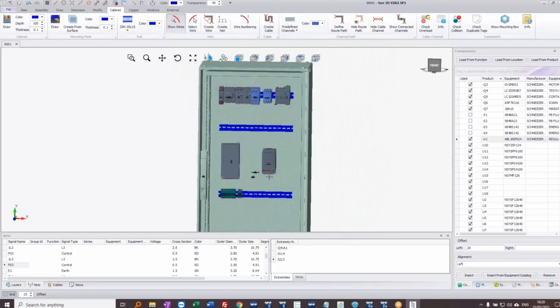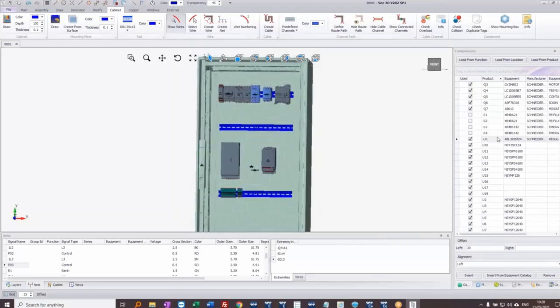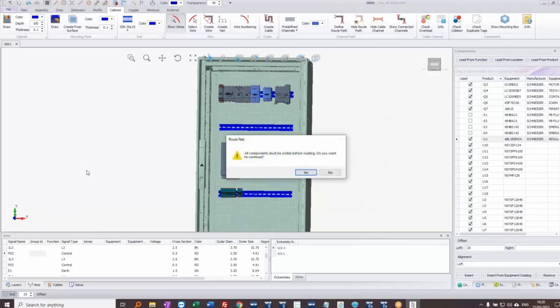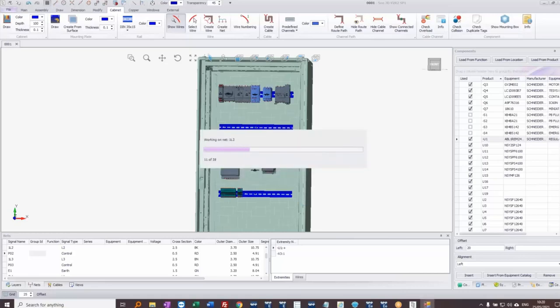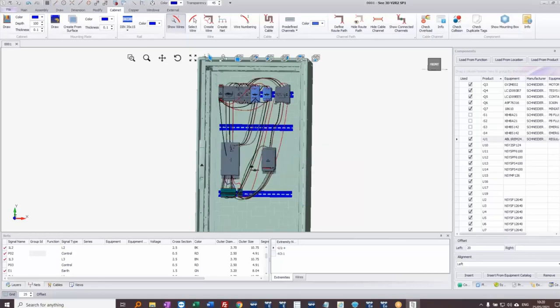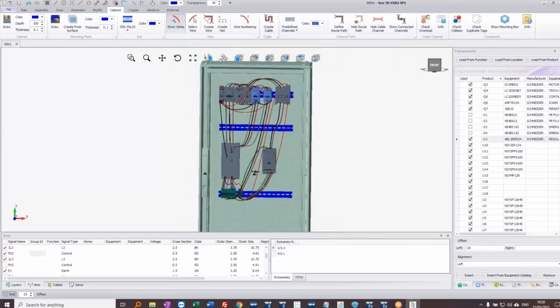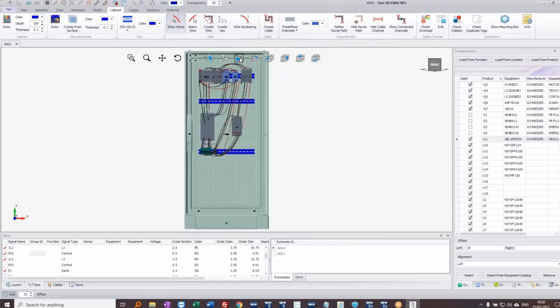I've placed most of the components that go on the backplate. Push buttons and motors would be placed outside the panel. To check how these are connected, I right-click on the nets and choose 'Route all nets'. It warns that everything must be visible for routing — I confirm Yes. I can see a rat's nest of wires, but there are no wiring channels yet — I've forgotten to add those. Let me go to a front view.